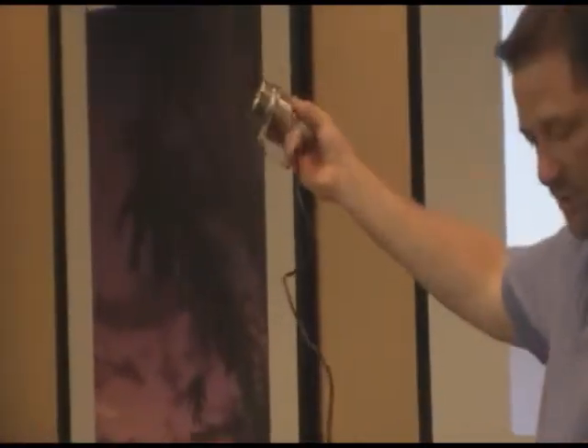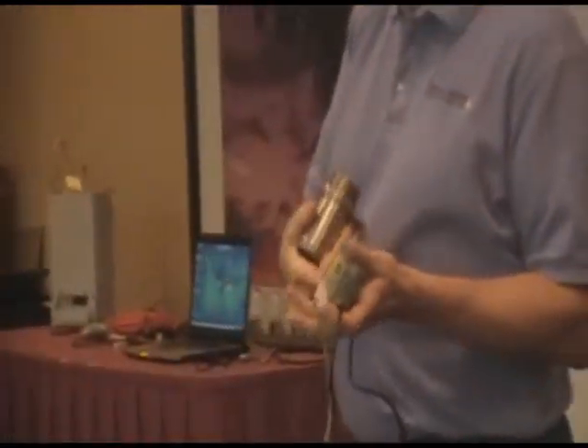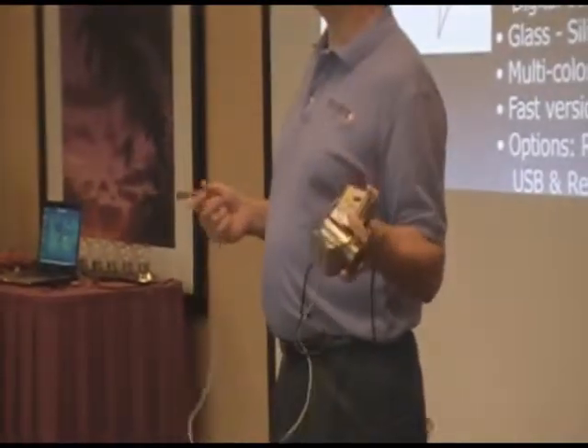We just have the sensing head. You have to buy a specific cable length with this — we cut the cable and it drops about 0.1 to 0.2 degrees C per meter. So this has a limitation of about 50 feet from the sensing head to the electronics box. Here you have all the outputs: J, K thermocouple, voltage outputs, milliamp outputs straight from this box that are switchable. This particular one has a USB board in there, so it's powered by your computer.